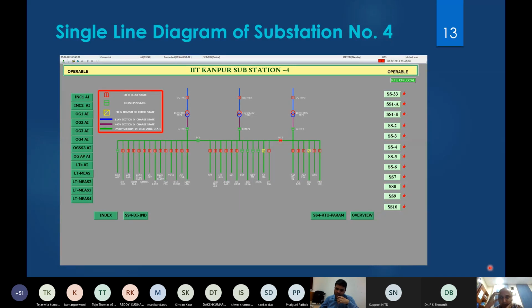Everything is available in real time. The way it works, the RTU polls the transducers every 2 to 3 seconds, and that data is communicated to the control center along with a timestamp.